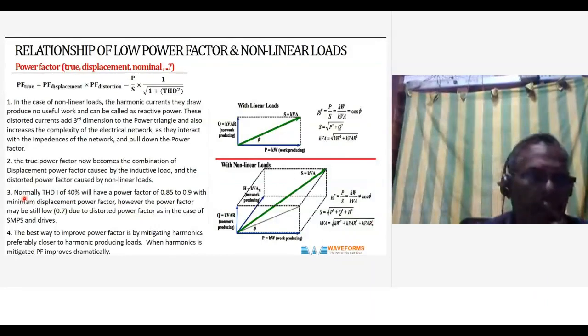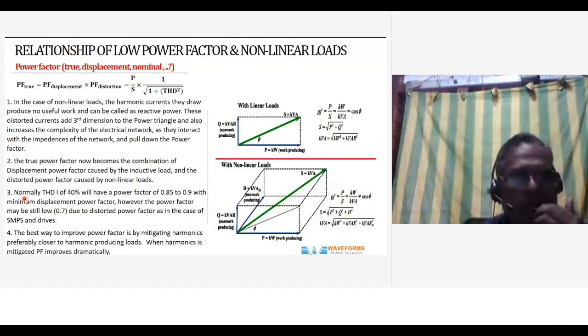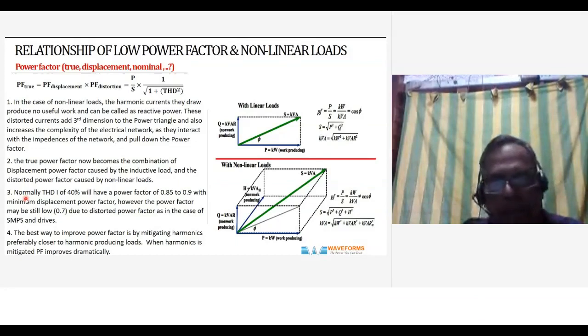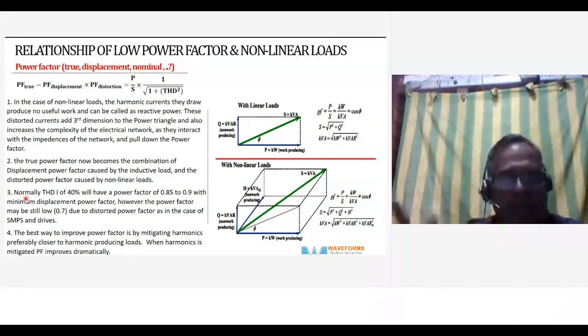In the case of non-linear loads, the harmonic components produce no useful work and are called reactive power. This distorted current adds a dimension to the power triangle and also increases the complexity of the electrical network, as the harmonics interact with the impedance of the network and pull down the power factor. When you have the third dimension, just adding a capacitor will not solve the problem. It will not solve the problem. You have to mitigate harmonics to improve power factor.